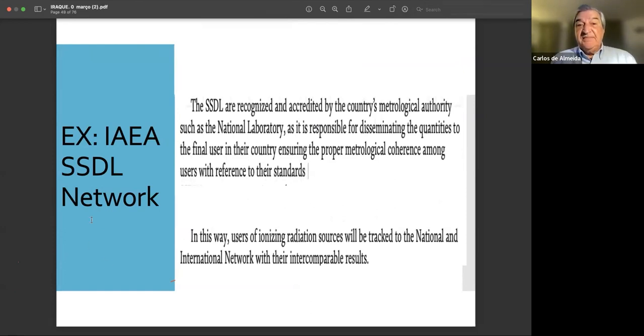So this SSDL is recognized and accredited by the country's metrological authority, and I'm sure in Iraq you have one. And it's not only responsible to disseminate the quantity, but also to follow the users. When we provide, as our lab does, for instance, for high dose rate iridium-192, we provide a calibration coefficient for the well-type chamber.